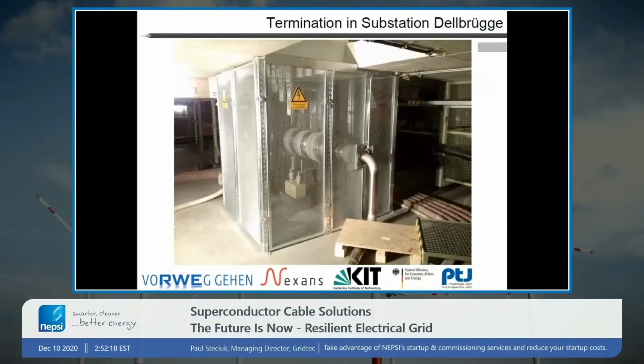Here's the termination. This installation was set up so that people could visit the substation and see the installation. So they elected to put the termination in a way that's visible, with this cage around it, so people can walk in and look at it. But this is the basic idea of the termination of the cable. So you can imagine this termination orientated vertically and put inside a cabinet, and that's what we're doing in other projects.